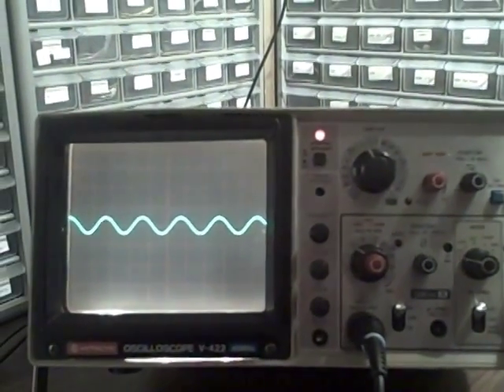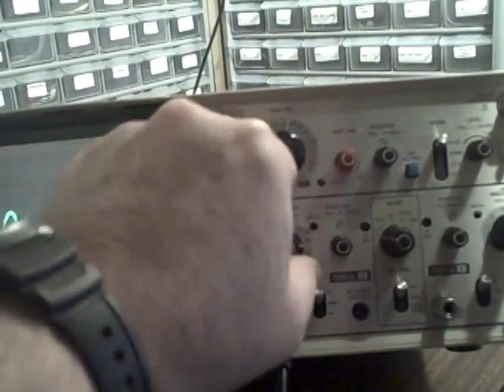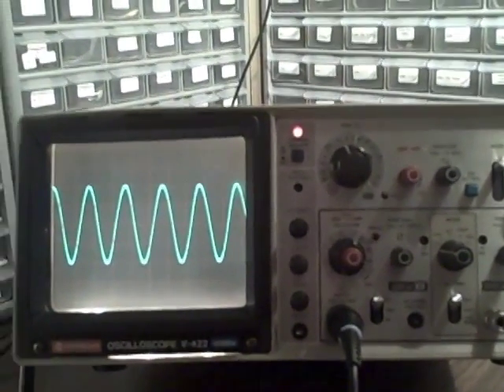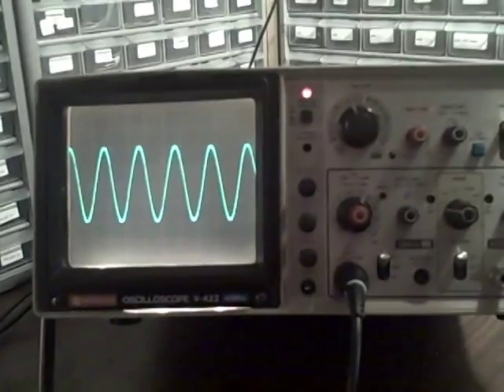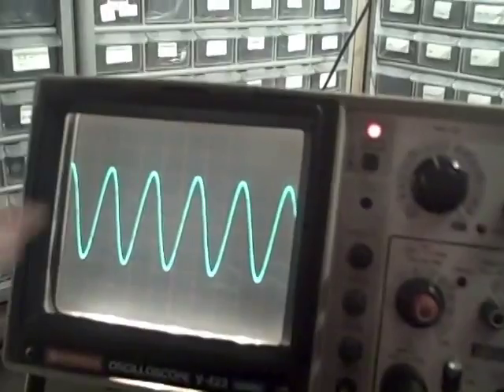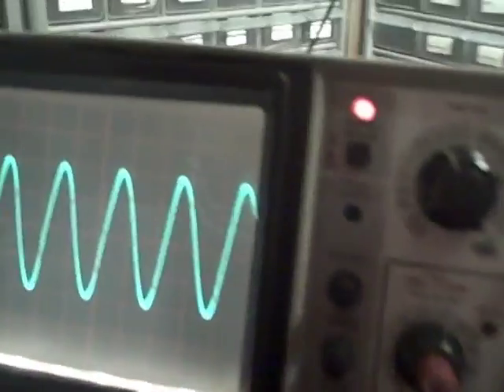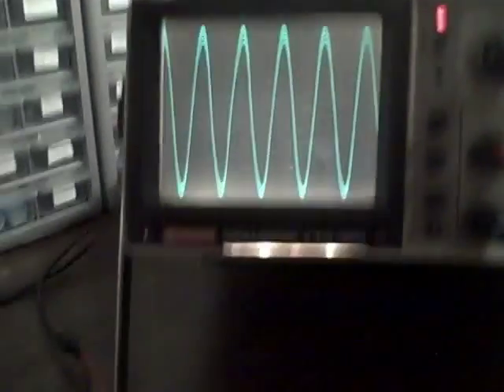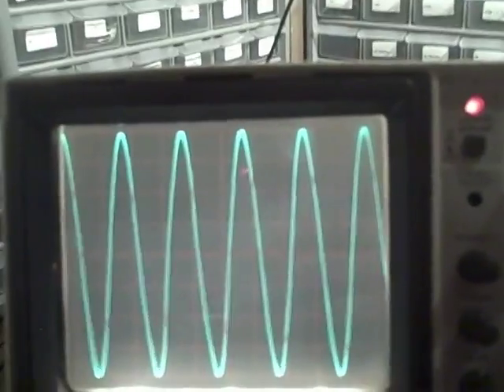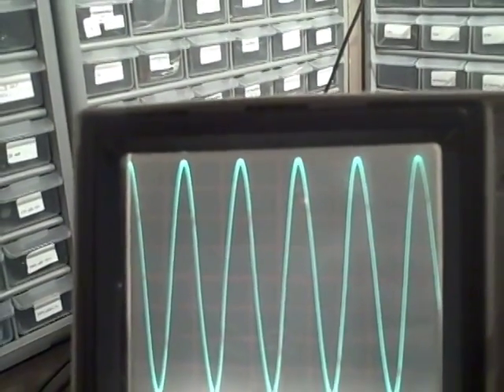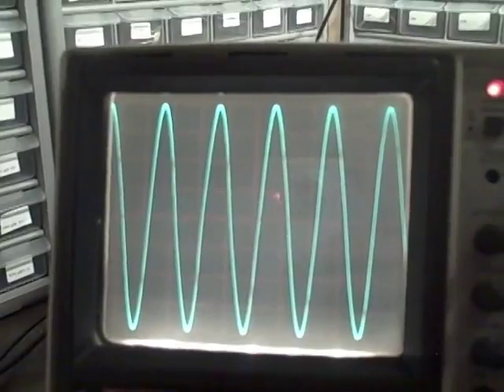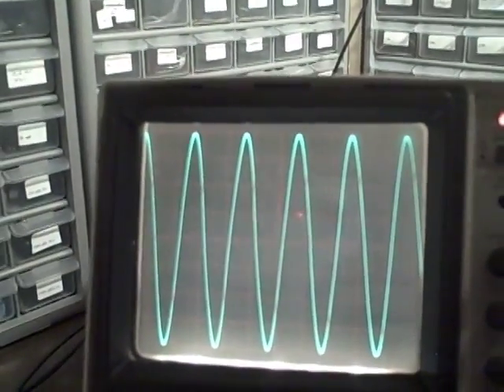Okay, so let's put ourselves back on divide by 10. We're going to take ourselves back down to the most sensitive range, and we're going to come up 1 range. We are now at 10 millivolts per division, and we're going to change our voltage to 40 millivolts so that we span 4 divisions here. So give me a moment. Okay, we now have 400 millivolts coming in from the calibrator. We are dividing it by 10 at our probe, and we are showing on the 10 millivolts per division scale, we got 10, 20, 30, 40 millivolts up and down. So 40 millivolts, which is what you'd expect. It's 1/10 of 400 millivolts, and that's what we had coming in.